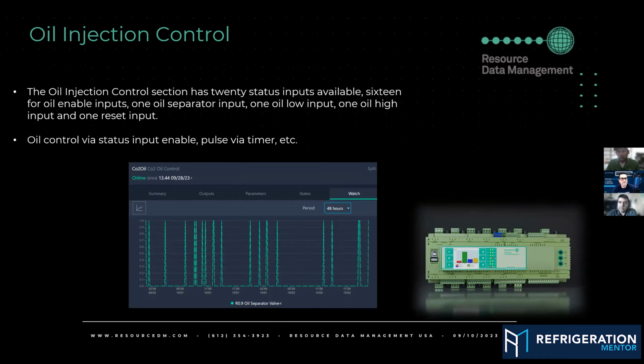Cool. Yeah. Oil injection is pretty simple. It can be done via status inputs. There's an oil separator input. There's high, low level inputs. All this stuff is configurable. You can use whatever status inputs you want. So you can control off an enable input. You can pulse it via timer. There's various settings you can do. It's pretty simple. That's not a very complicated section to set up, really.